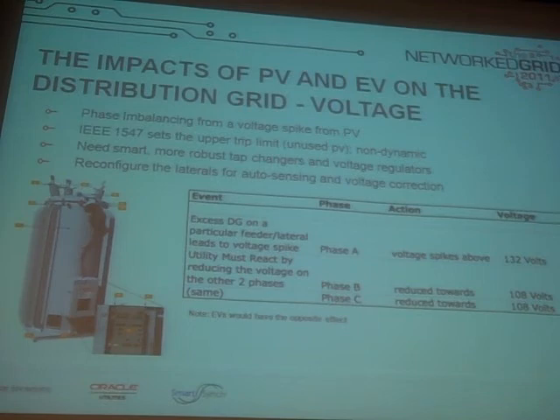Along with that, at the substation you need more robust tap changers and voltage regulators on the grid that can work much closer to real time to balance the effect of DG and EVs. What you would like to do is, using a tap changer or the voltage regulators, when phase A spikes to 132, the utility wants to drop phase B and C closer to 108 to bring them back into level.